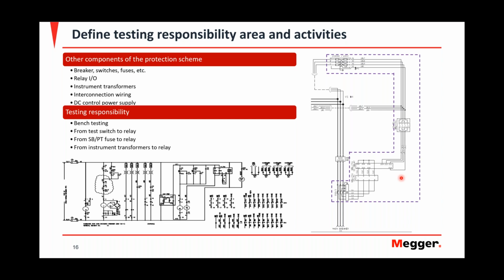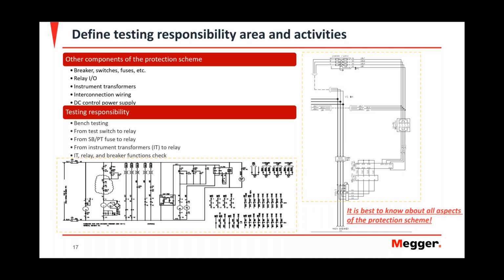Or you test the CTs, the PTs, and the relay. In that case, you're checking the whole thing, so that requires more test equipment. Now you need a CT test set and a PT test set, in addition to a relay test set. Or you could test the whole scheme, including the breaker scheme. Then you do a functions check. You make sure that every single leg of your scheme functions properly: all the lights, your trip coils, your close coils. Now you're testing the breaker itself. You could do your hipot test, your contact resistance test, your bottle integrity test if it's a vacuum bottle breaker, etc.